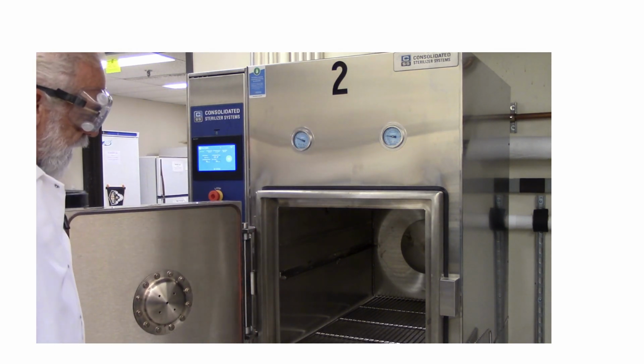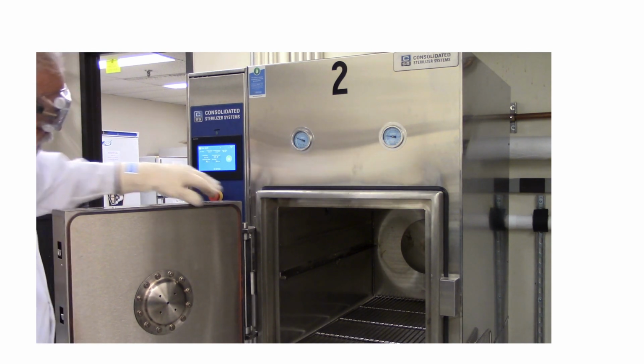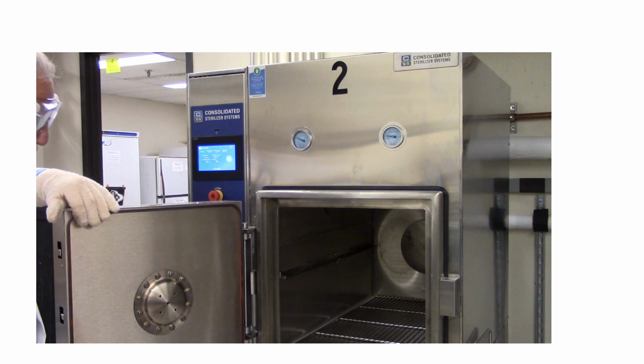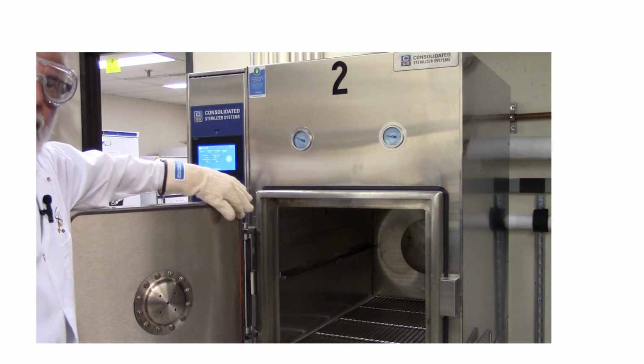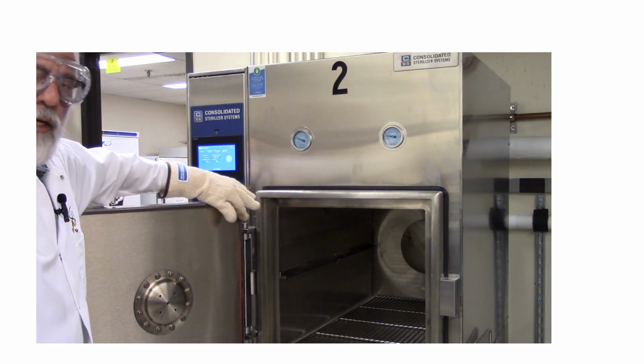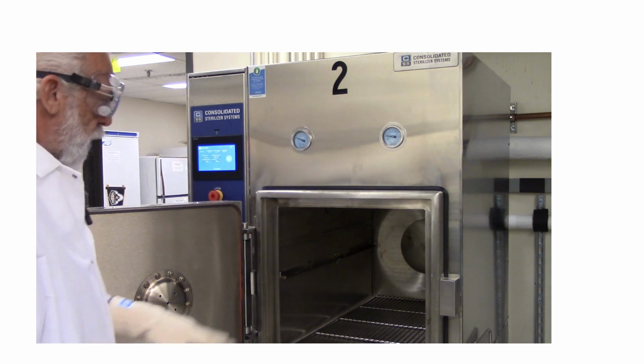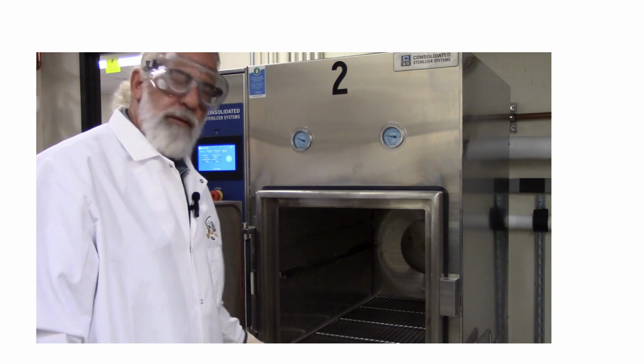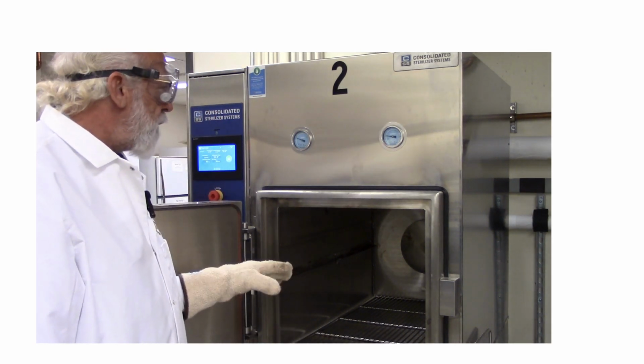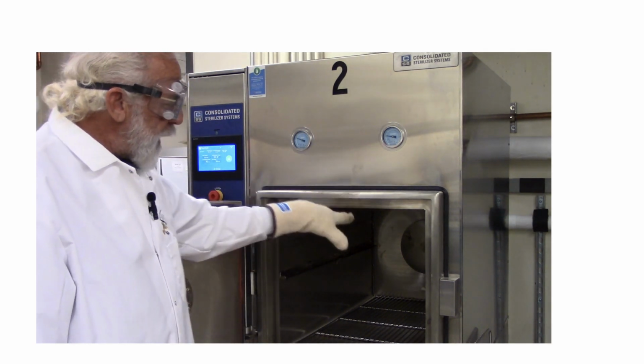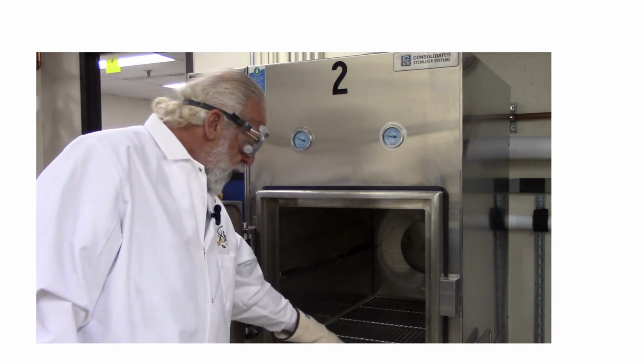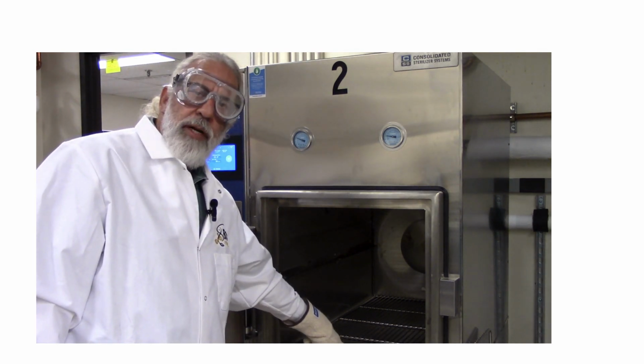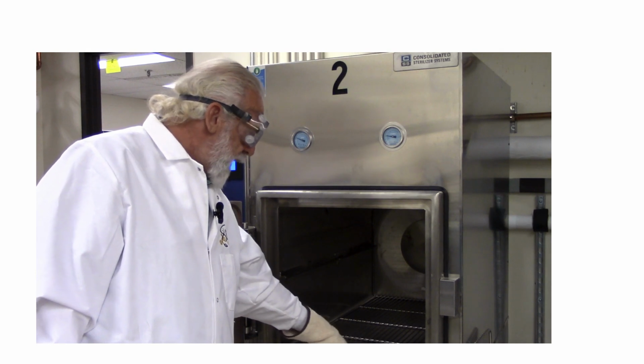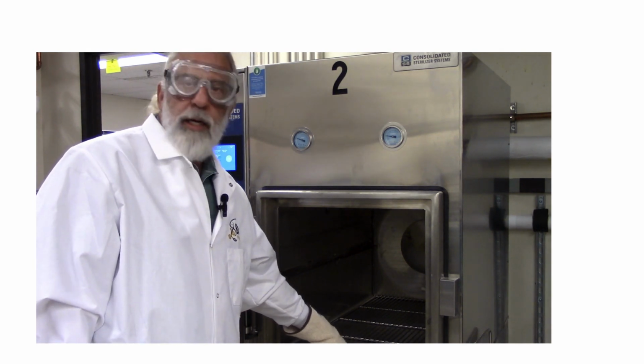Inside the chamber, you can see it's nice and clean. Got a flat gasket, and if you were to notice any damage to that gasket, we need to know that or it won't work right. You don't want to see a lot of debris inside of it. The way this autoclave will work, it injects steam at the top, and it forces air out this drain at the very front of the unit. If this drain is plugged, it's not going to operate correctly.